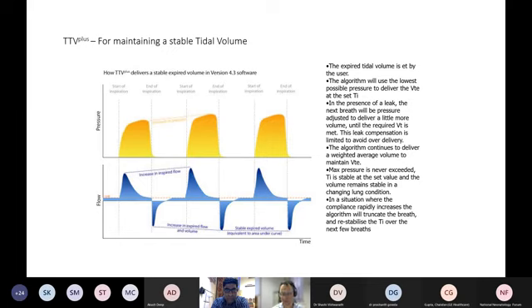If you imagine in pressure ventilation, such as on the SLE 2000, we set a pressure and the volume that is delivered to the patient's lung is really a function of their respiratory system. If their respiratory system is quite tight, the volume is going to be quite small. If their respiratory system is fairly compliant, that volume is going to be greater. The pressure itself won't change, and you as the user won't be aware of how much volume is being delivered on a breath-by-breath basis. What the flow sensor allowed us to do was to regulate the tidal volume, and it regulates the tidal volume by automatically adjusting the pressure on each breath in order to maintain a stable tidal volume.